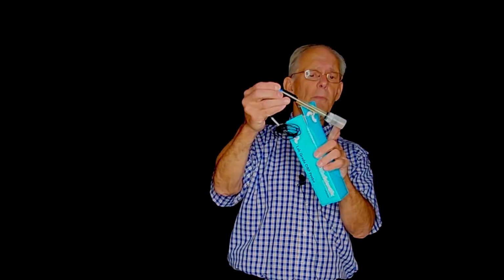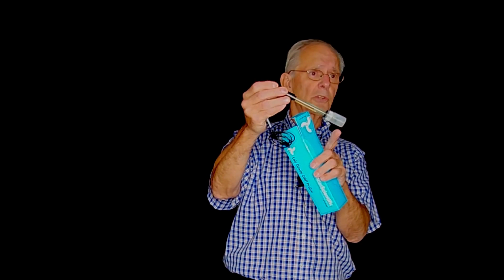This is what they call a galvanometric sensor, and it connects to a small amplifier that changes the signal into something the PLC can read. This one's called ORP, oxidation reduction potential. The bottle on the end is a preservative liquid, because these go bad if left sitting in air. It's primarily used in wastewater to measure another factor. Then we have one called dissolved oxygen, which measures the level of oxygen in water, whether wastewater or clean water.